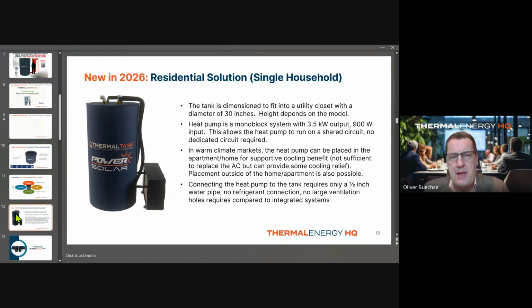So this is designed for a single household or even an apartment. It allows the owner to take advantage of all the same design and operating principles we just went over. The heat pump is not integrated into the tank by design, in contrast to some of the other heat pump water heaters you see. That allows you to place it in another part of the home or apartment, capture that cooling benefit, or even move it outside. There's no ventilation required on the install.